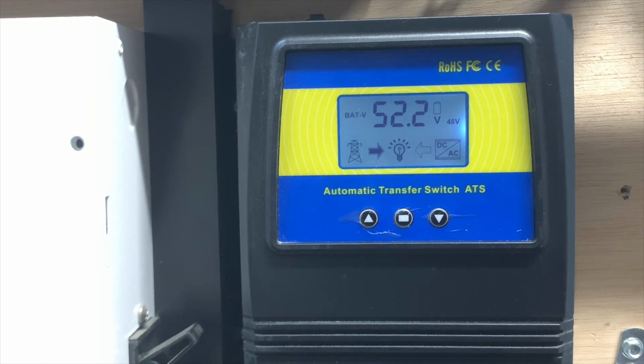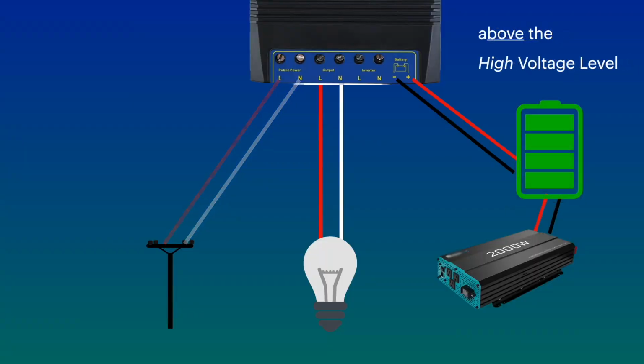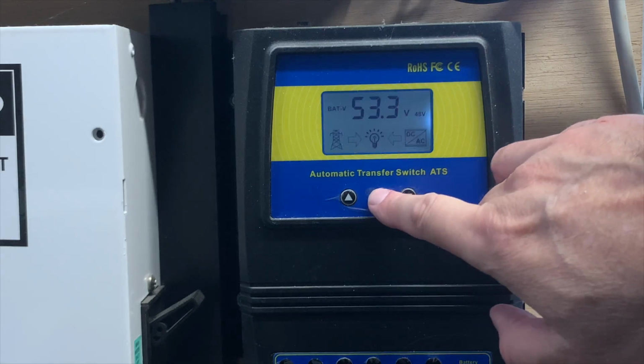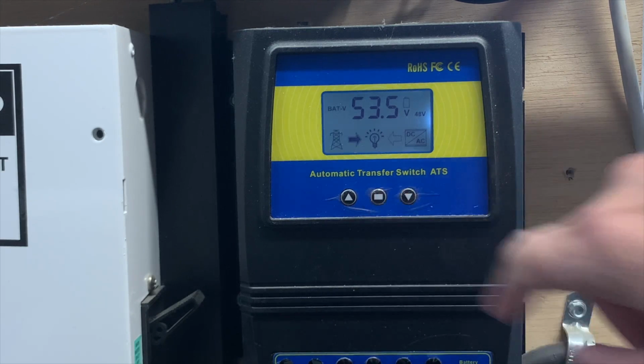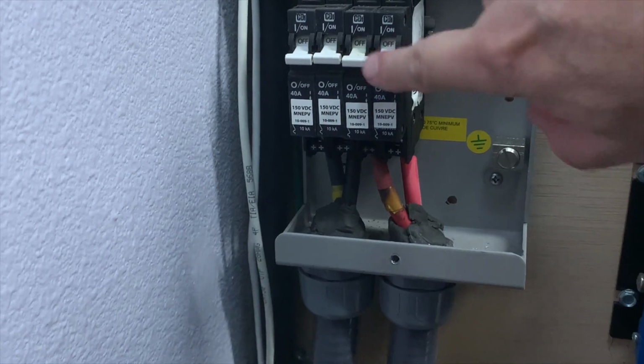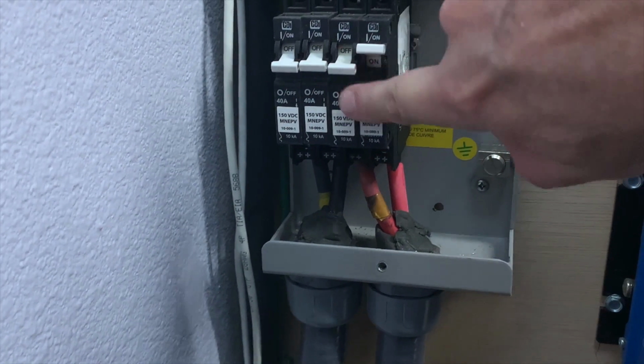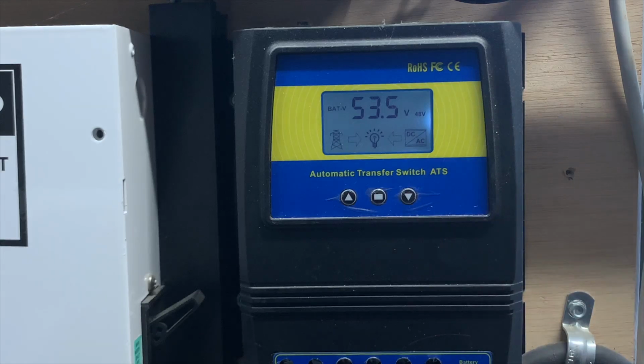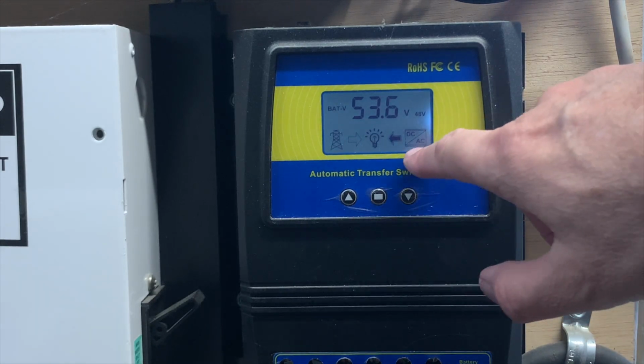Now, to get this to switch back over to the inverter, we will use something called the high voltage switch. When the battery gets above the high voltage level, we will reconnect to the inverter for power. To get to the high voltage switch, you press this center button twice. And I've got this set for 53.5, and I'm reconnecting my PV to recharge the battery. You can see the little arrow here. We're still on grid. And there, we just switched back over to the inverter.